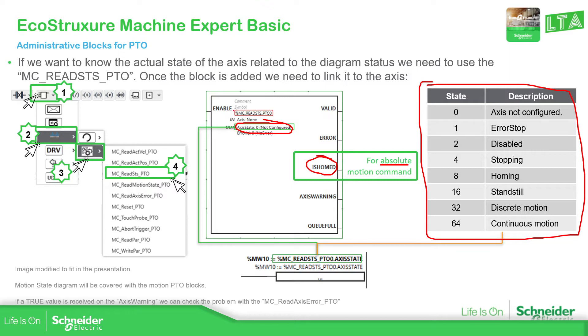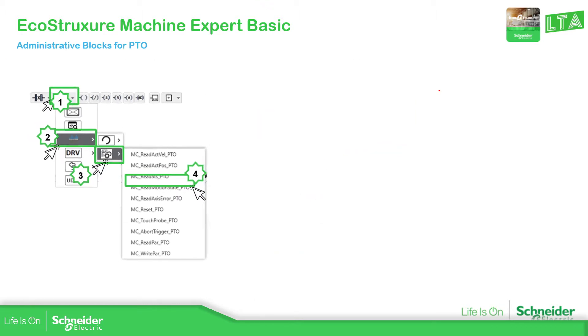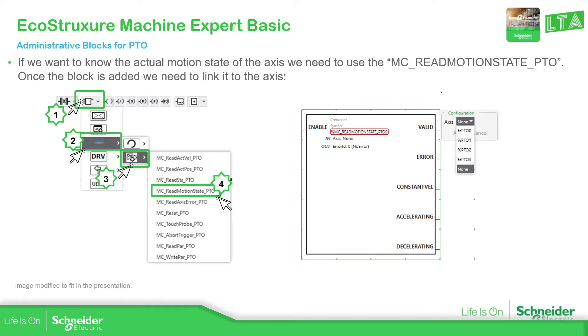In order to display axis state in the HMI, we just need to use the name of the instance with .AxisState and move this value to a %MW variable. We also have the readMotionState, which basically says if it is at constant velocity, accelerating, or decelerating. You just need to enable this with a variable and then link it to an axis, and that's all.